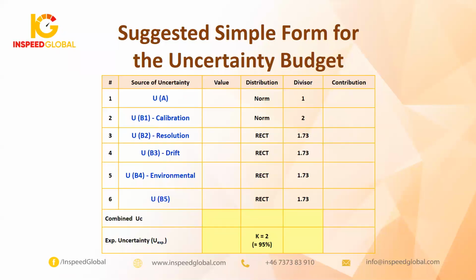After that, you can go directly to drift. What's the meaning of drift? As with resolution, related to type B, as you see, there is no effort performed by yourself. You go directly to the equipment and mention this value. For calibration it is constant, and the resolution is also a constant value. For drift, you can get 2 calibration certificates, one for 2019 and the other for 2020, and take the maximum uncertainty minus the minimum uncertainty, and divide this value by 1.73.